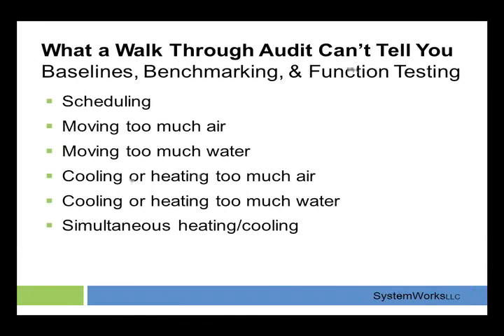Scheduling is probably the number one thing that you can't see when you walk through a building. Unfortunately, we find a lot of schools that are running more hours than they need to run the equipment. It's a double-edged sword. It cuts you because it costs more money to run it, and it shortens the life of the equipment because it's spent more hours running. So when you actually lower your utility bills by using scheduling correctly, you can actually increase the longevity of the piece of equipment as well as lower the bill.